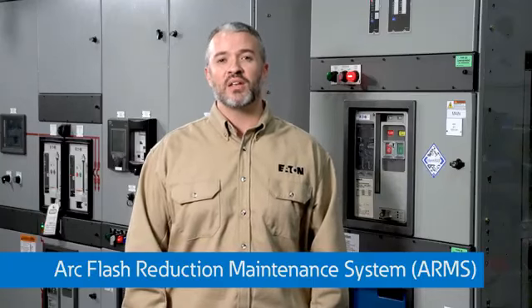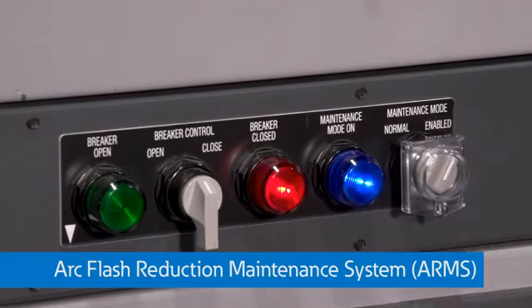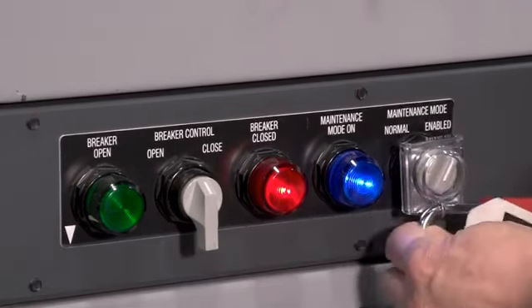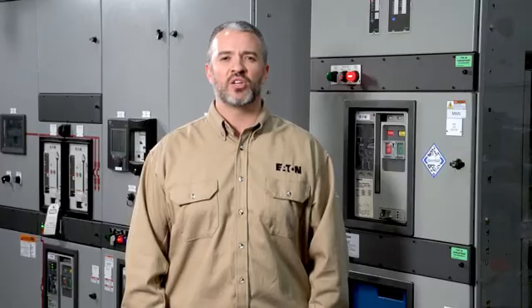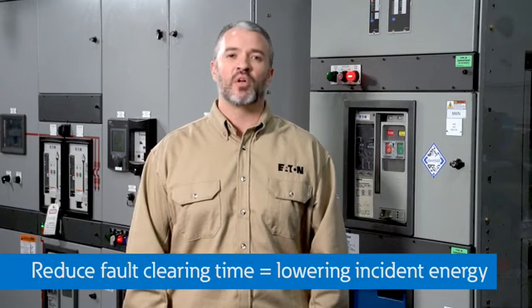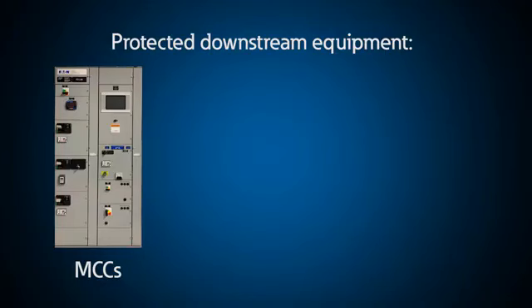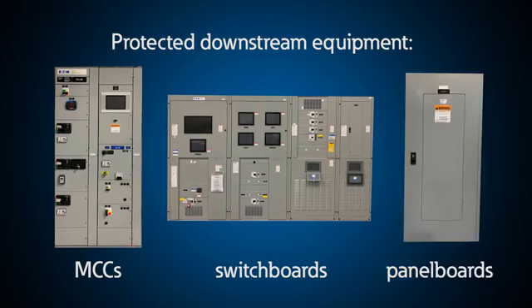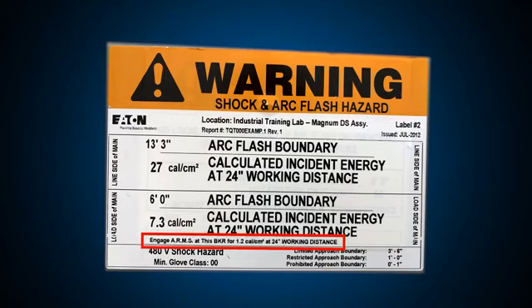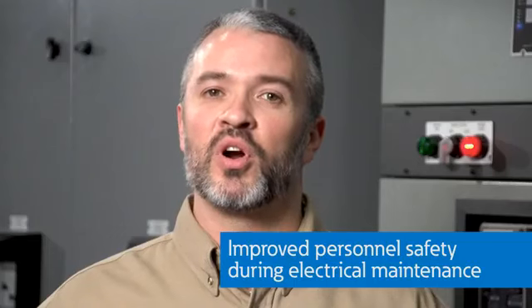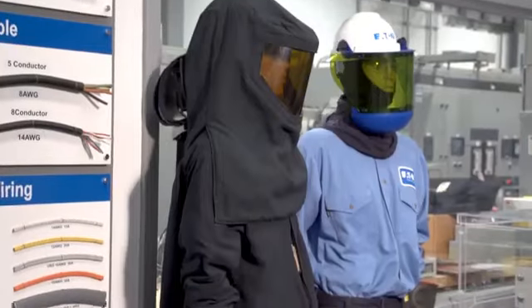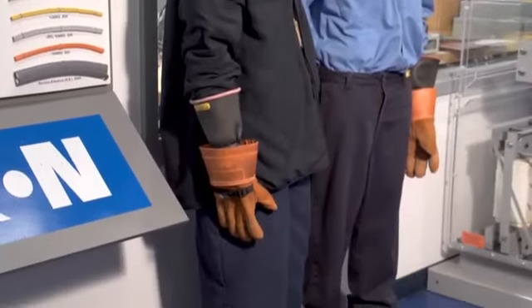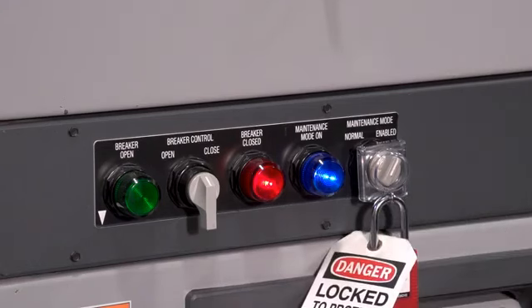Eaton's Arc Flash Reduction Maintenance System, or ARMS, is available on low voltage power circuit breakers and many of our molded case circuit breakers. This system uses patented technology to reduce fault clearing time, lowering the available arc flash energy at the connected downstream equipment like motor control centers, switchboards, panel boards, or other equipment. The system may be activated at the breaker or from a remote location. The result is a reduction of the incident energy during equipment maintenance, allowing for improved personnel safety while eliminating the need for higher levels of costly personal protective equipment, or PPE.